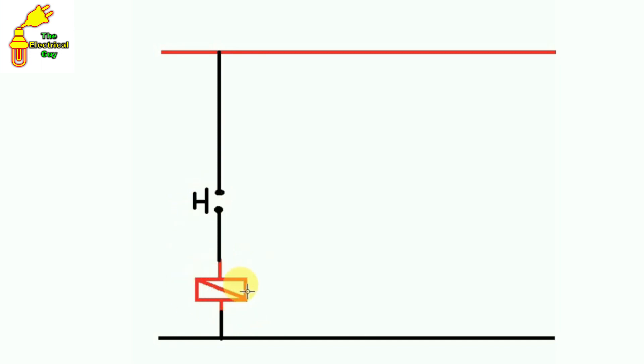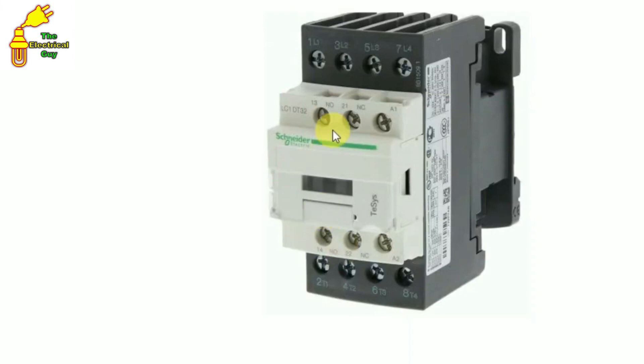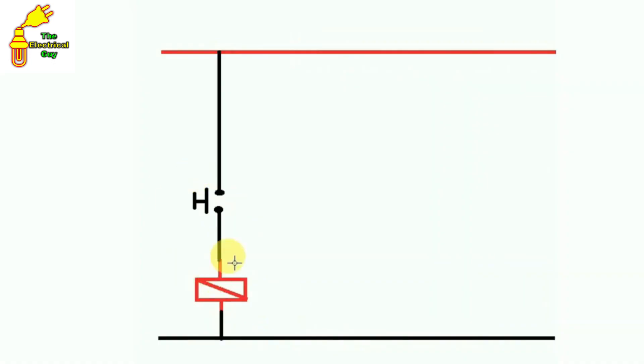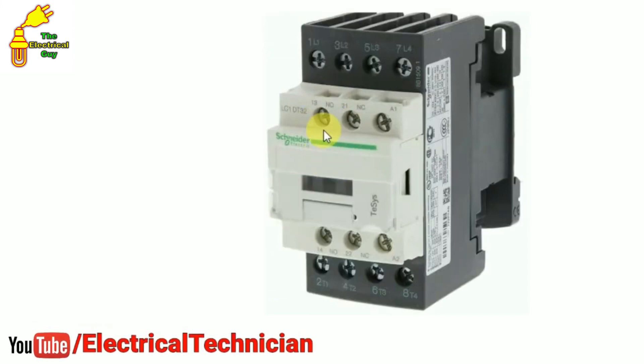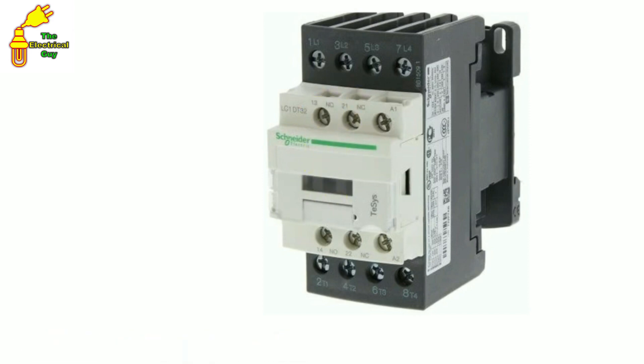For this we use the auxiliary contact of this contactor. In this contactor there are two auxiliary contacts — NO and NC. The question is which auxiliary contact we should use so that this circuit can hold the contactor on. We will use the NO contact, and I am going to tell you the reason why.